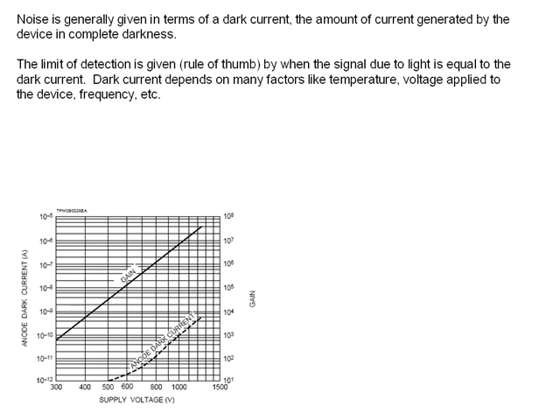Okay, so let's go ahead and solve a problem. Let's say we have a wavelength that we're trying to detect of 400 nanometers, and let's say we are putting V equals 600 volts on our photomultiplier tube. If we go back and we looked at the gain at 600 volt supply voltage, we see that point right there. There's 600 volts. And our gain looks to be about 10 to the fifth, or 100,000.